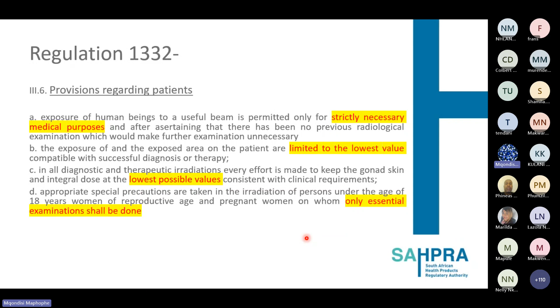Okay, so as I mentioned, regulation 1302 will list for us all the instruments that are supposed to be regulated. But just so you know, every machine that is used in the country must be licensed for import, meaning all the machines that are listed in regulation 1302 must be licensed for import. And we do not license machines that are secondhand in another country and are coming to this country, unless they are fully refurbished. Fully refurbished meaning the manufacturer of the equipment will have to certify that machine as fully refurbished.